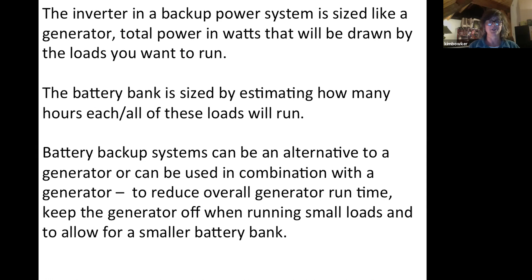The last point I want to make is that they're not one or the other. You can use a battery backup system and a generator, and there's some good advantages to that. Number one, you run your generator less. Number two, you could keep your generator off when you're running small loads or overnight, and then you can have a smaller battery bank. So it always comes down to the question of what you're trying to run and for how long.